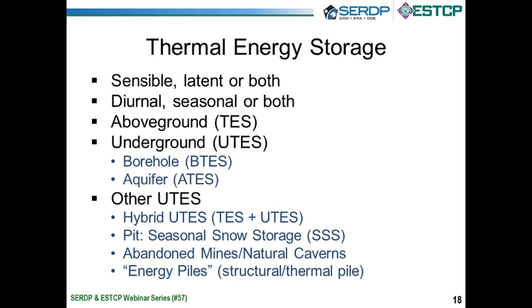Other forms of UTES are hybrid UTES, meaning maybe you're doing it above ground and below ground. There's a project in Calgary. The only other BTES system known to us in North America, in Calgary, is a warm storage BTES, but they also have above ground tanks. So they're doing short term storage above ground and long term storage underground. So that might be considered a hybrid UTES system. In Europe, they sometimes use pit storage, literally digging a pit, dumping snow in the pit during the wintertime, insulating the top, maybe some plastic pipe down in the pit, and then circulating water through that to melt that snow, in other words, a latent phase change, and cooling buildings with it.